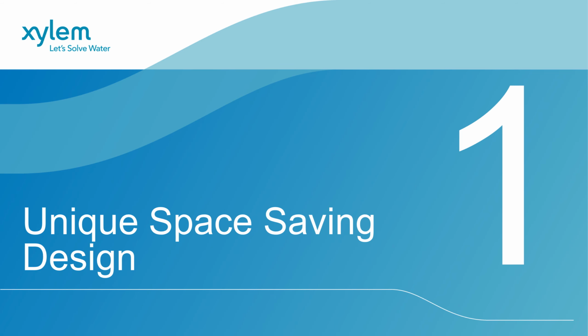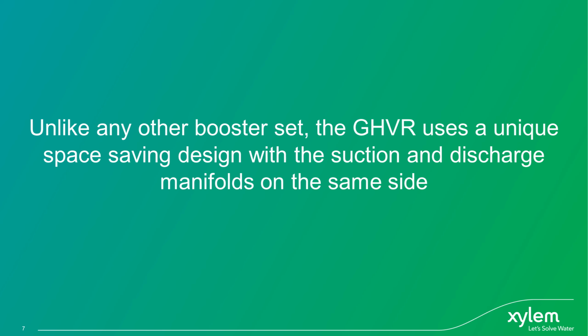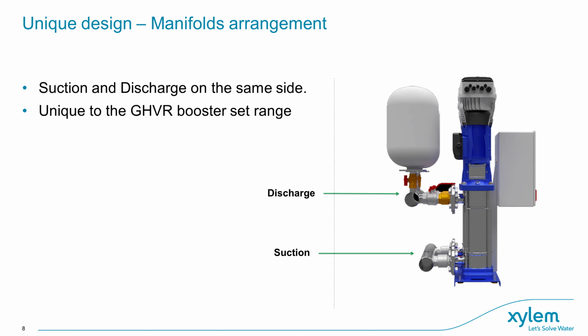Let's start with the design of the GHVR. To summarise, unlike any other booster set on the market, the GHVR uses a unique space-saving design with the suction and discharge manifold on the same side. So in this slide, you can see the side profile of the set showing the suction manifold on the bottom with the discharge manifold just above.